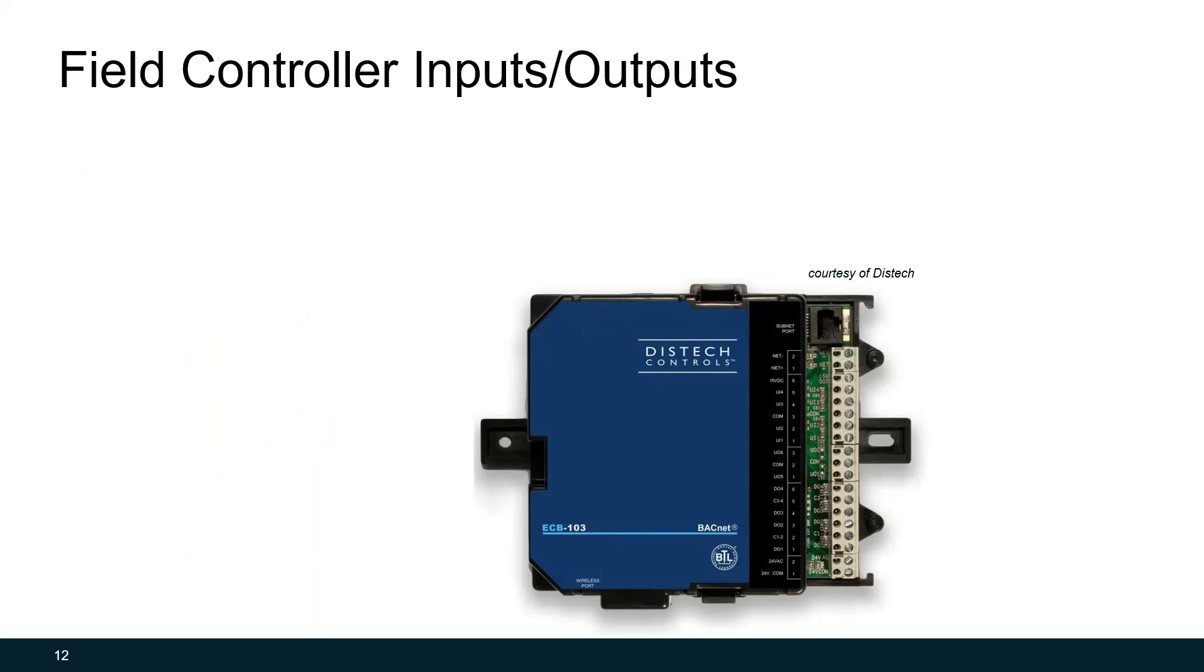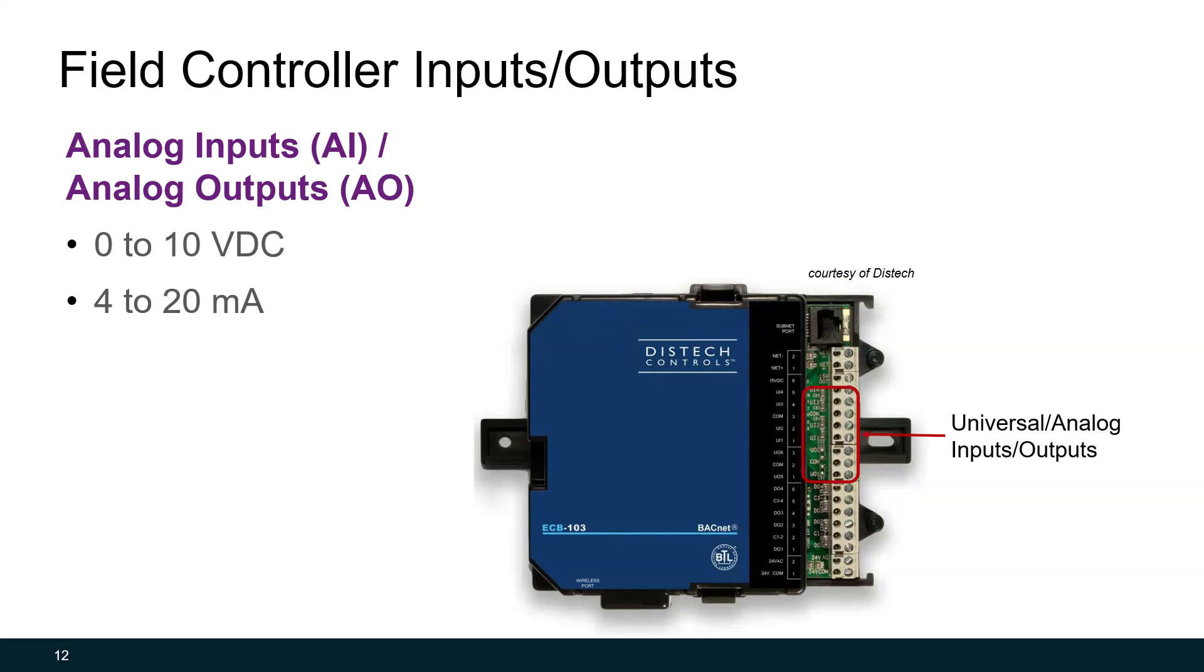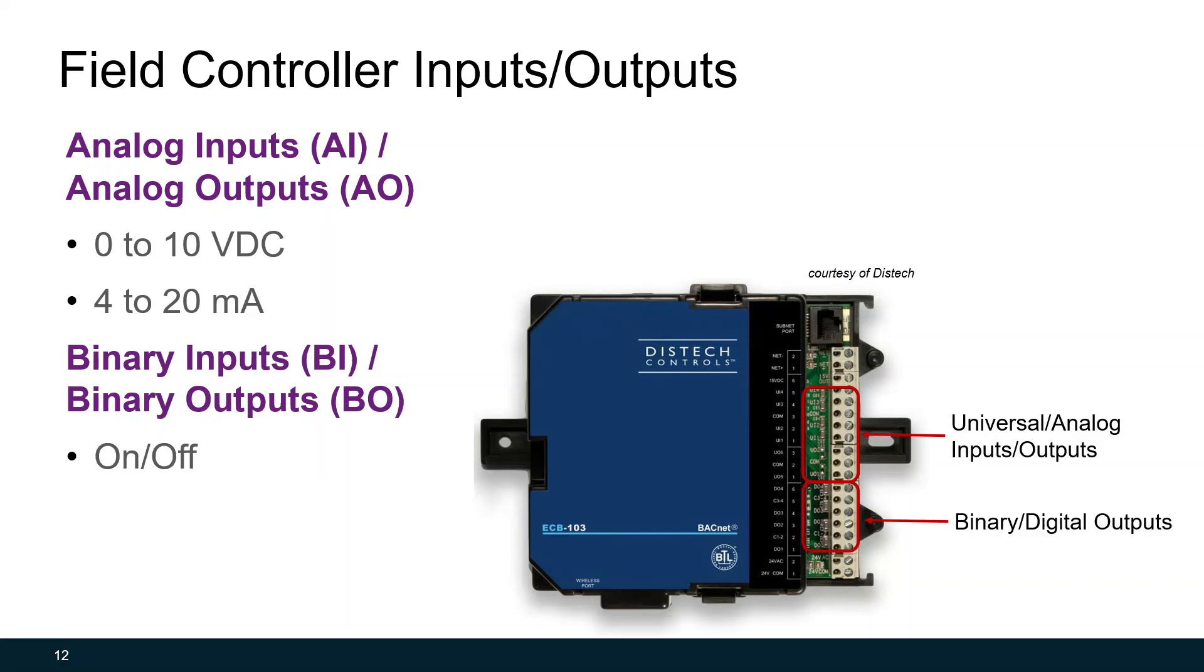Here's an example of a field controller. This one is by Distech Controls. You'll see that it's essentially a miniature computer. On the right is a board for inputs and output signals. This is where we physically wire in sensors and control devices to communicate with the controller. There's usually a section for analog. Sometimes they're universal inputs and outputs. Universal just means it can accept analog or digital. Analog signals usually are transmitted in a direct digital control system where you would use this device in 0 to 10 volts DC or 4 to 20 milliamps.